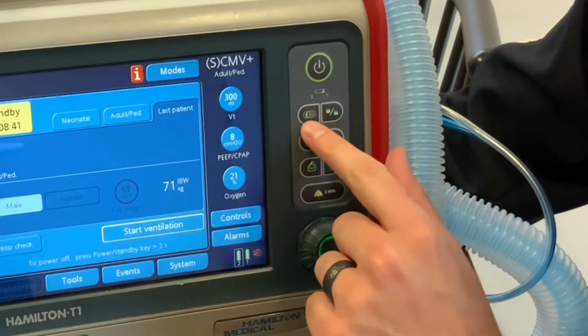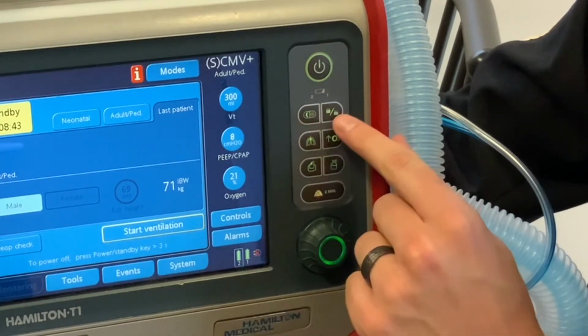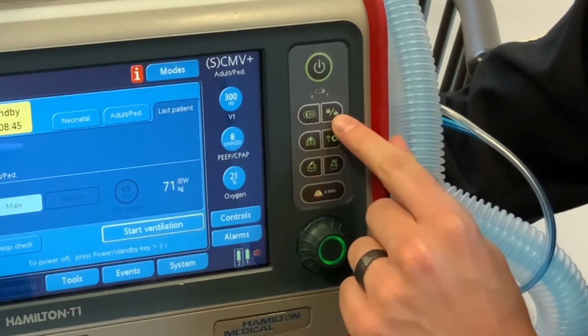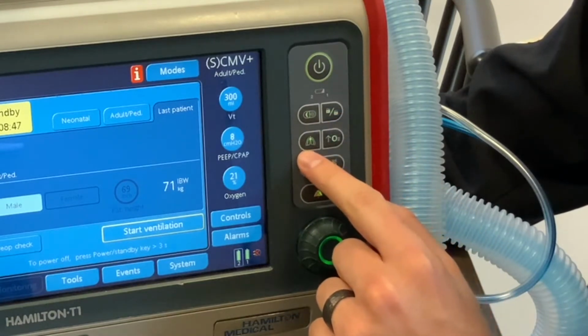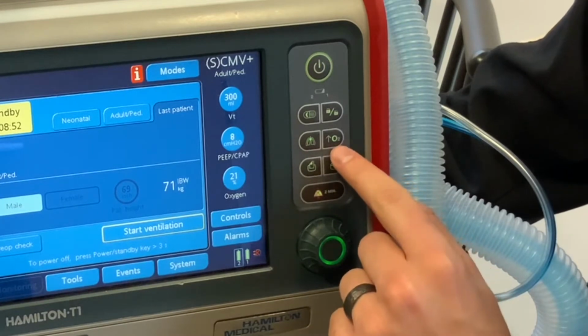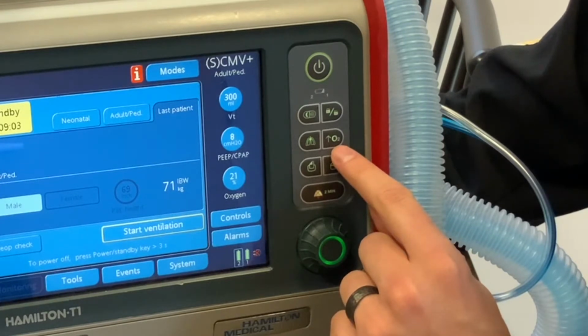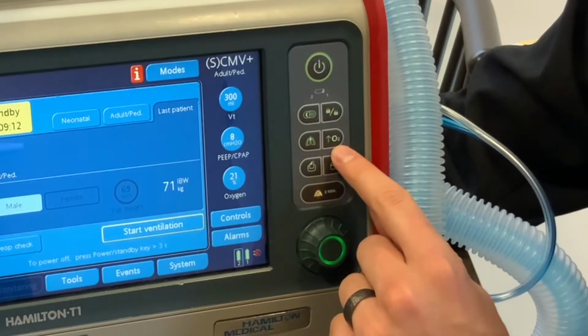Below that, we have the day-night key, screen lock and unlock key, manual breath or inspiratory hold, increase FiO2. In adults, this increases the FiO2 to 100% for 2 minutes. In the neonatal mode, this increases the FiO2 by 25% for 2 minutes. For example, if the child was on 50% FiO2, it would be increased to 75% FiO2 for 2 minutes.